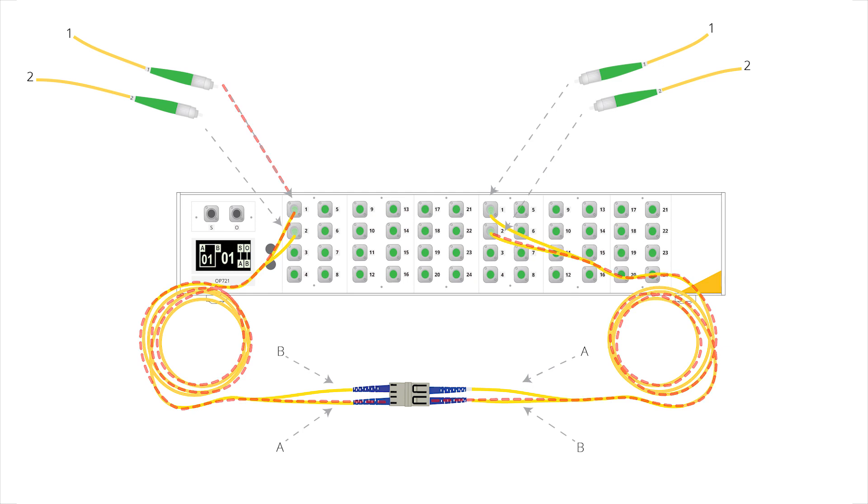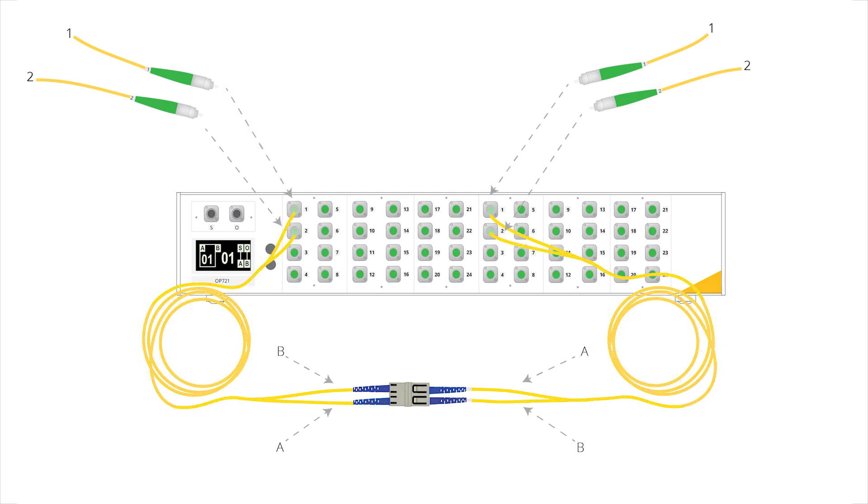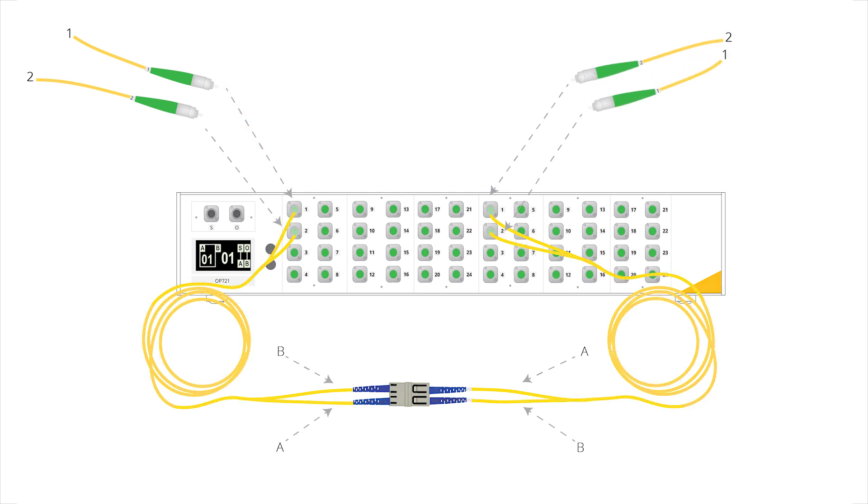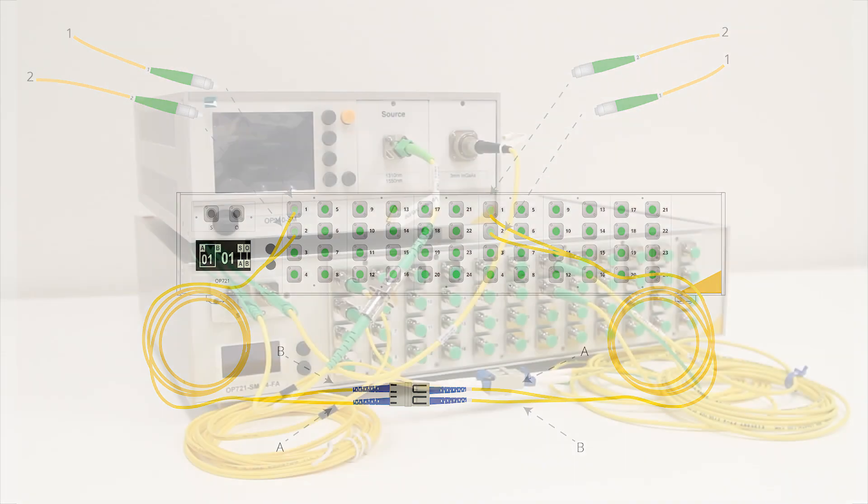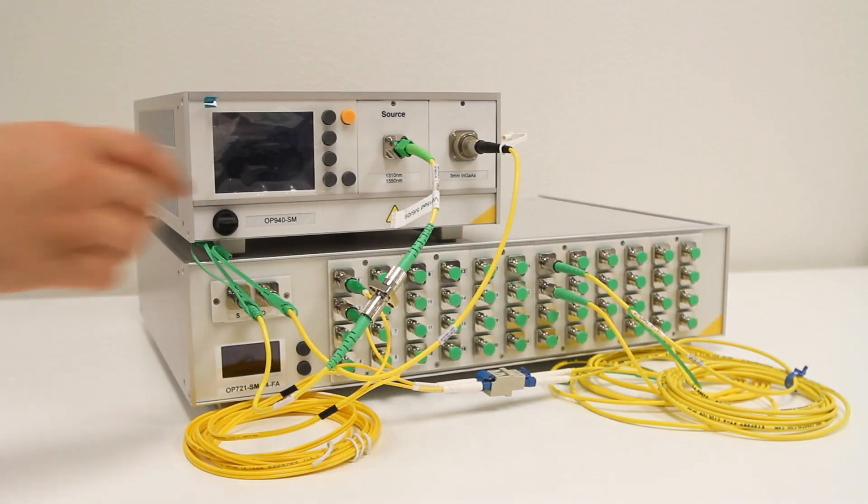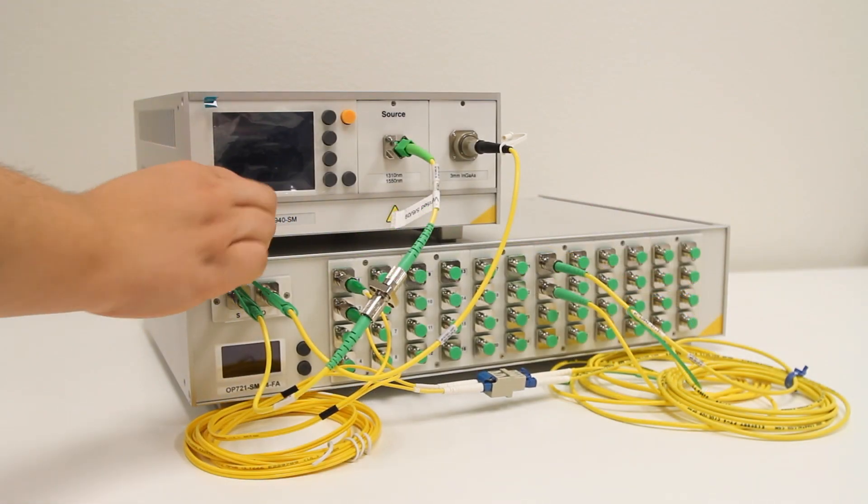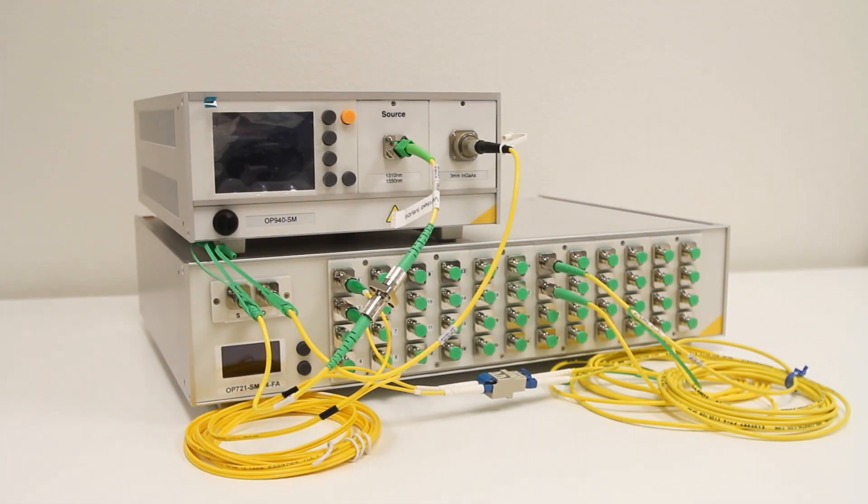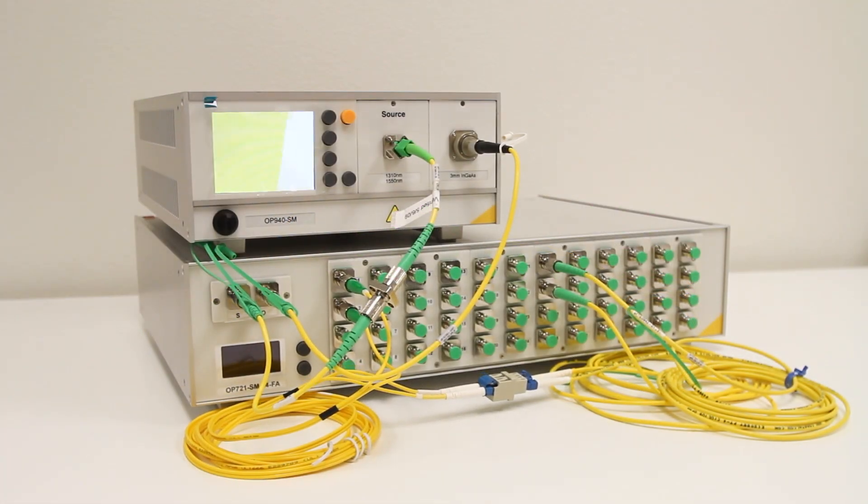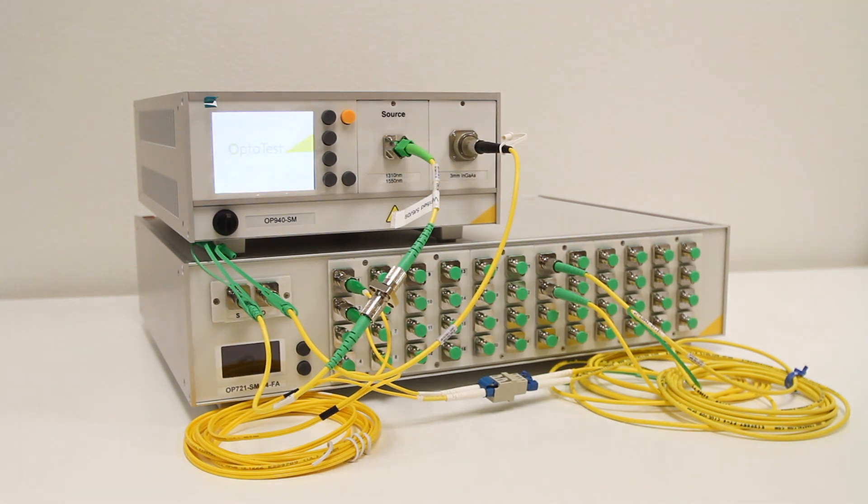The simplest way to fix this is to swap the connectors on the right-hand side of the OP721. This ensures that the light emits from channel 1 on the left and is received by channel 1 on the right. Another option is to use simplex reference cables rather than duplex, as is done on the right-hand side of this test setup.